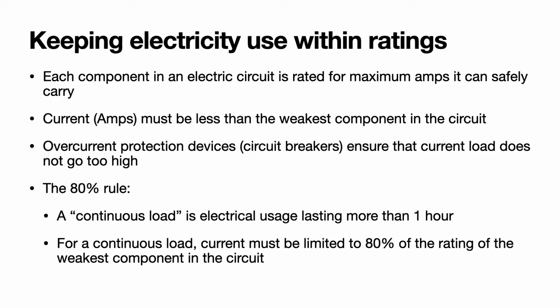What does this mean to keep electricity use within the ratings of the circuit? Each component in an electric circuit is rated for a maximum number of amps it can safely carry. And the current, or the amps, must be less than the weakest component in the circuit. So you might have a circuit of 10 components, 9 of which are rated for 80 amps, but if one of them is rated for 20 amps, then 20 amps is the maximum.